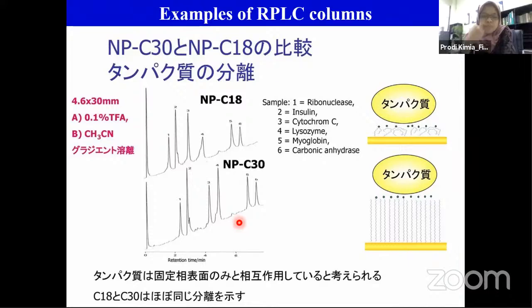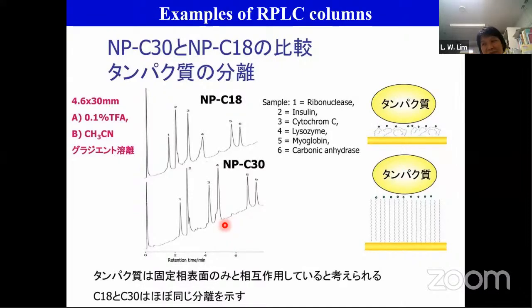Sometimes you can reduce this by using a different wavelength, so you can check your wavelength. If your wavelength is around 220, 230 nm, then it is normal to have a baseline like this if your eluent contains a mixture of acetonitrile and water.